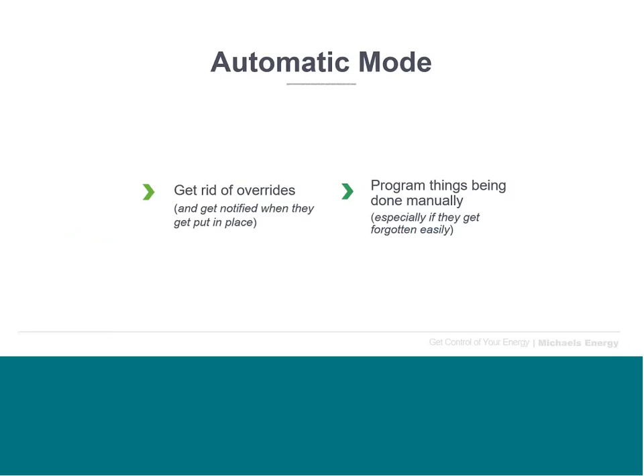Okay, the next thing is using more automatic modes. One of the big struggles that a lot of buildings may have, which is a little more hidden, is that there's a number of overrides that have built up over time. A lot of controls operators will have the ability to go in and manually override certain pieces of equipment and operate them in a constant way, which ultimately ends up causing some troubles and typically ends up pushing the energy consumption higher than it needs to be.